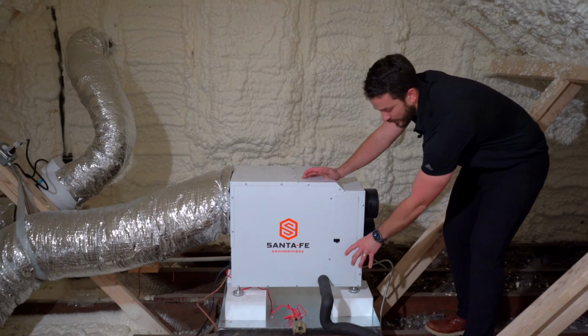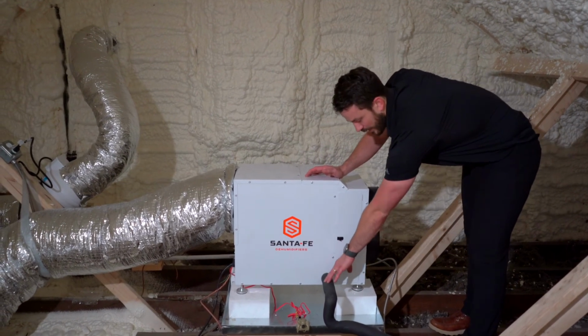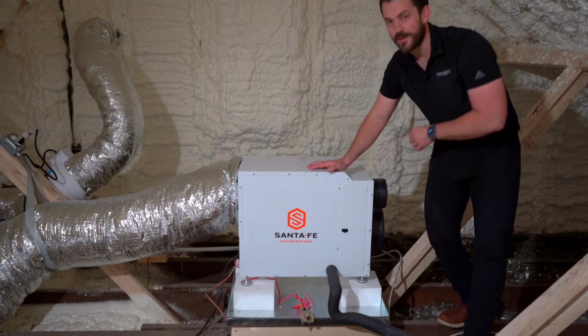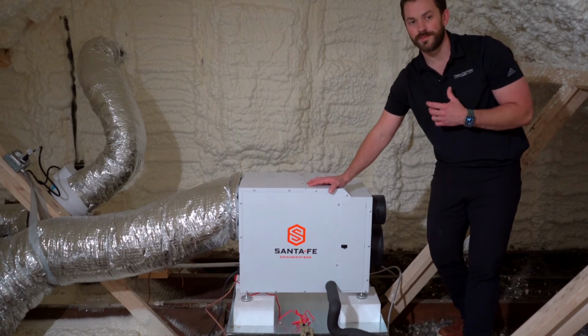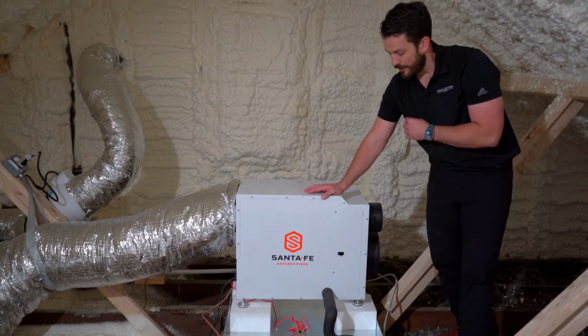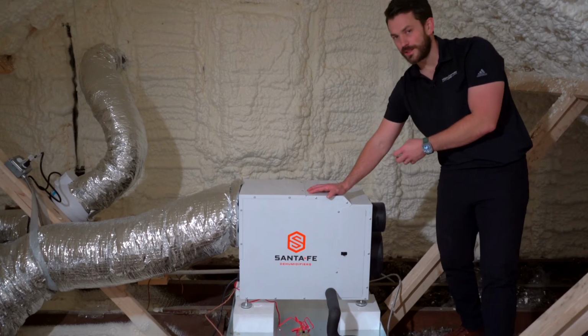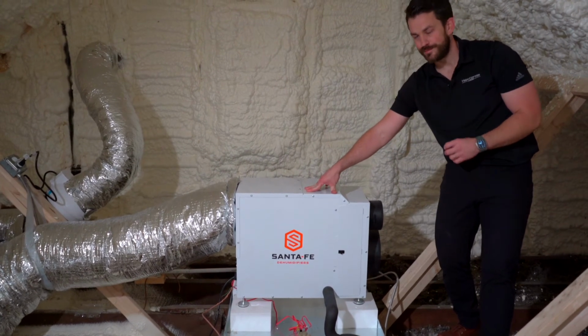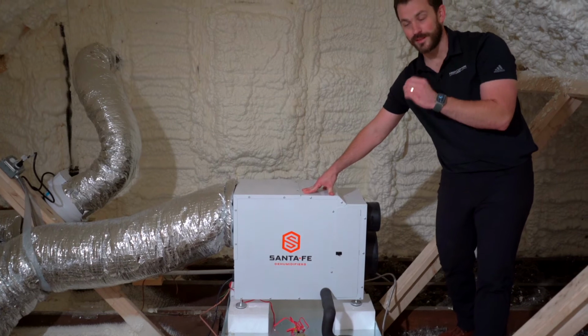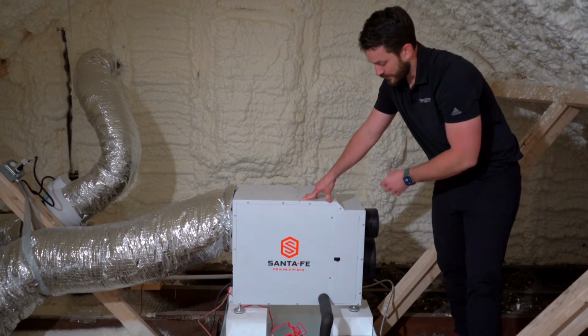Our condensate drain is plumbed out of the bottom, and it's gravity fed. Some of our other dehumidifiers used during construction have a condensate pump, but for a permanent installation like this, we try to avoid the pump just to eliminate that extra maintenance issue.